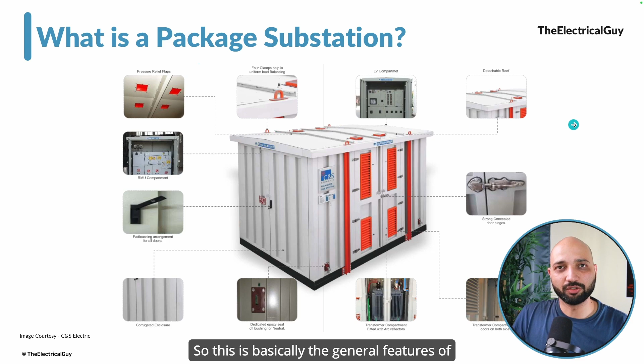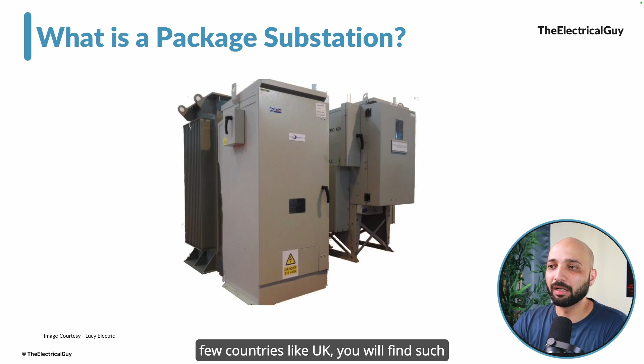Now it's not necessary that the package substation comes inside a container; it may look like this instead. You can see this is our ring main unit or RMU, via which we connect to the transformer. The backside is the transformer, and the front side is the low voltage panel, mentioned as 415 volts. This is also called a package substation, and depending on which country you are in, some countries like the UK mostly use this kind of arrangement.